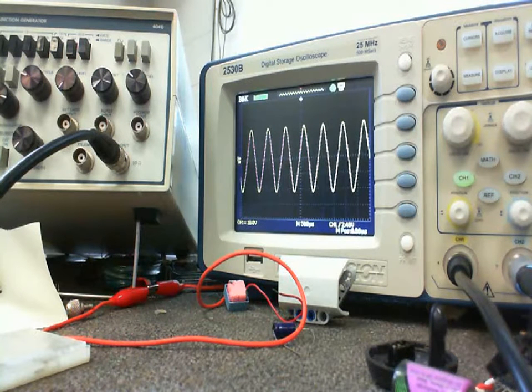Yes and no. Now we have slip rings - we have slip rings on regulated generators. This is not a regulated generator. What a regulated generator is going to do is maintain a constant output, no matter what, over a load range, right? You understand that? This we don't regulate, so we can use a permanent magnet.